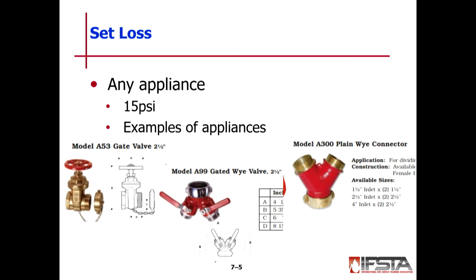So that first one there, just a gate valve, that's typically what you would see in a standpipe system, right? They'll be on the first floor. Inside the building, you'll have a Y or Siamese outside the building, and then every floor after that, where you hook up our high-rise kits, you'll have another one of these gate valves or OS&Y valves.